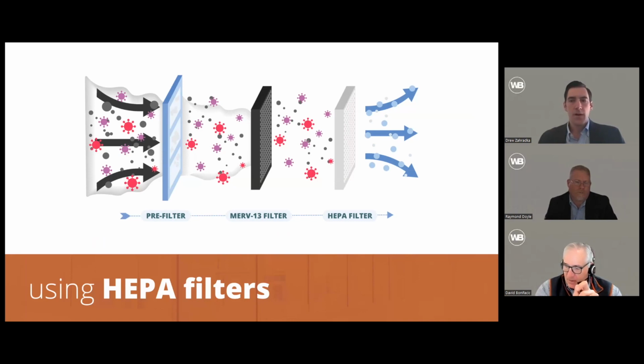Yep. So in terms of viral and biologics, in some of those spaces, depending on what the contaminant is, you would exhaust directly out of the room, so there's no recirc back to the space. Depending on the risk in the room, you may not have a recirculated air handling unit due to potential cross contamination. So you would have a once-through space.